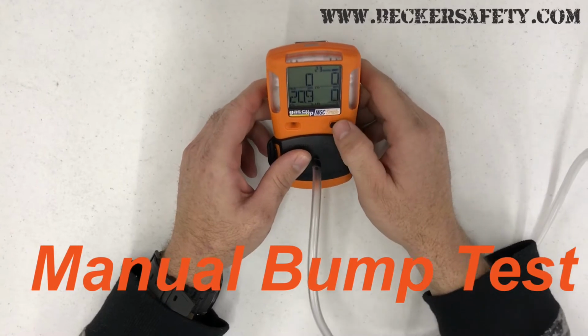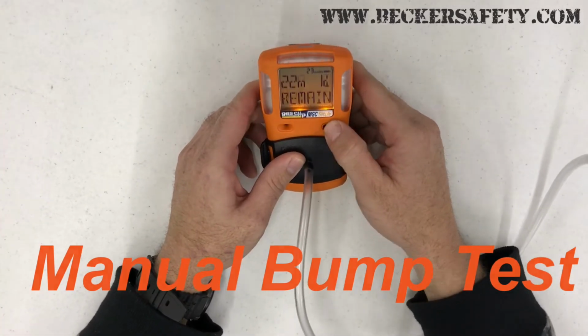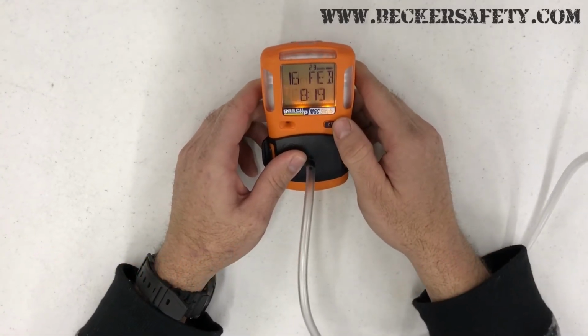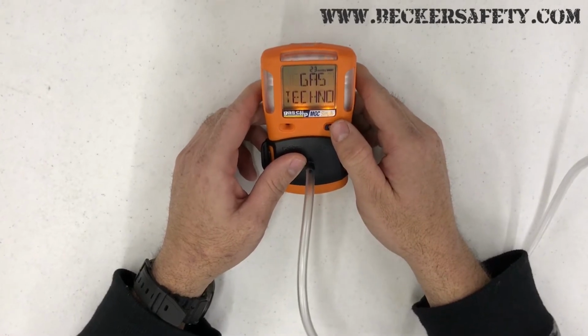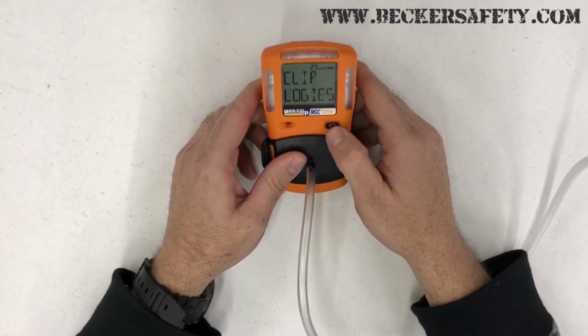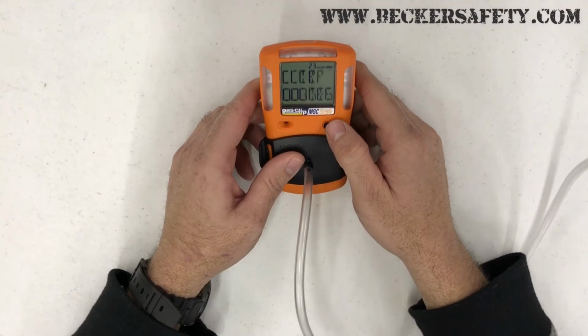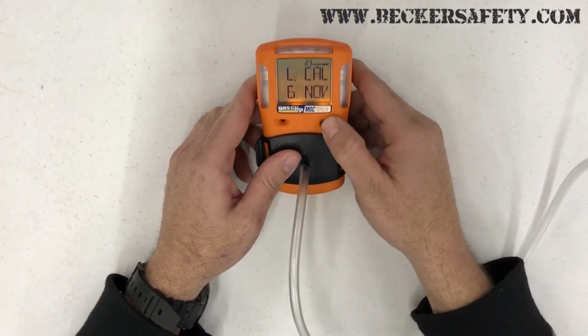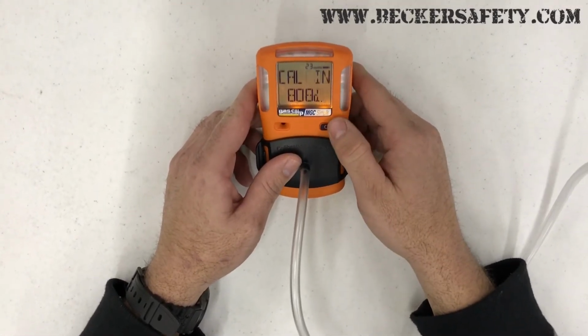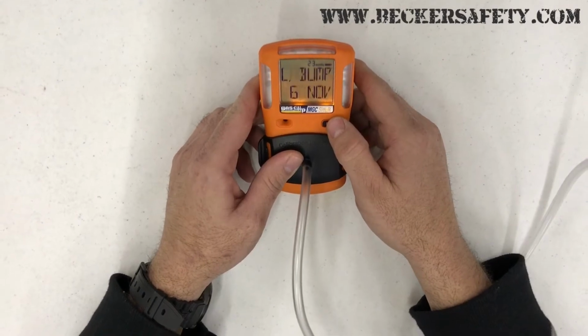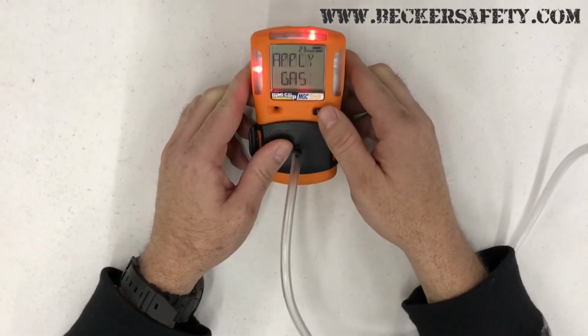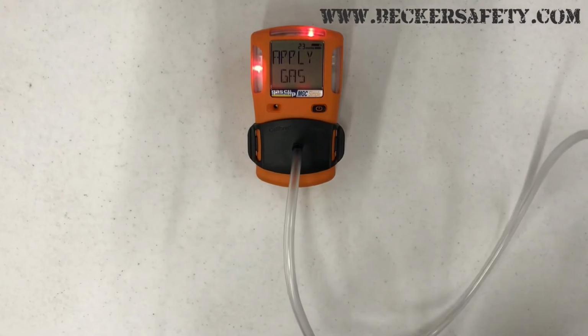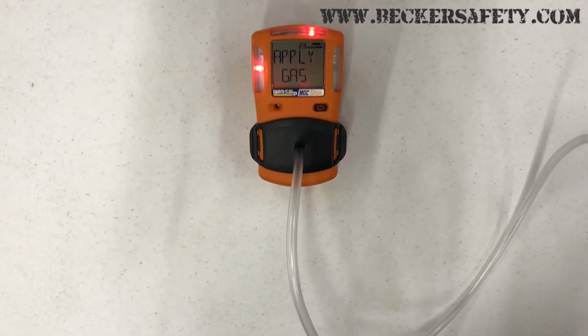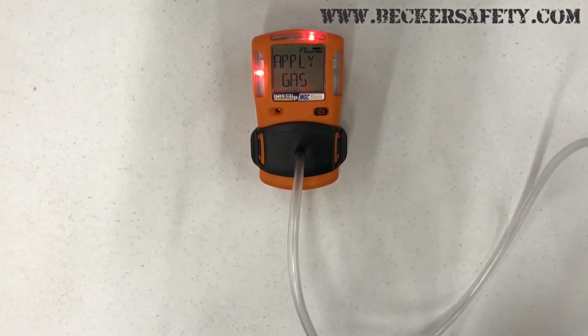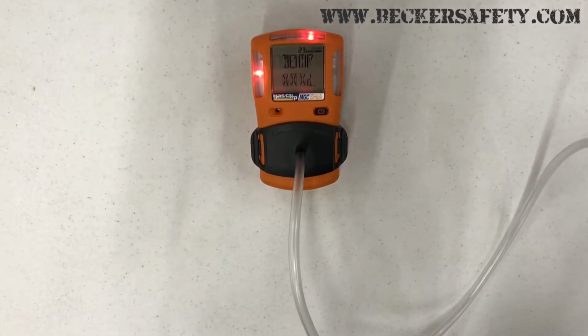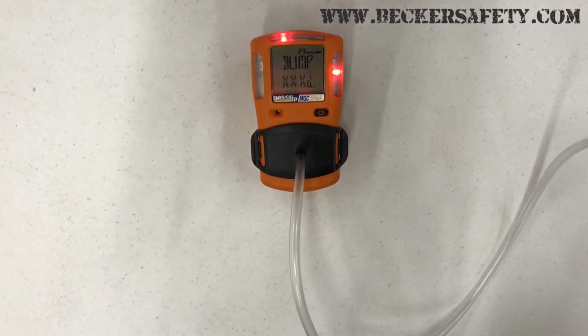In order to do that, you press your power button twice and it'll start scrolling through its information screen. Once it gets to show status, you need to hit the power button again. Show status, hit the button again, and then when it gets to the bump, you hit the button once again. It'll tell you to apply gas. You turn your gas on and then wait for the monitor to beep. Once it starts beeping, then you know that it's done.